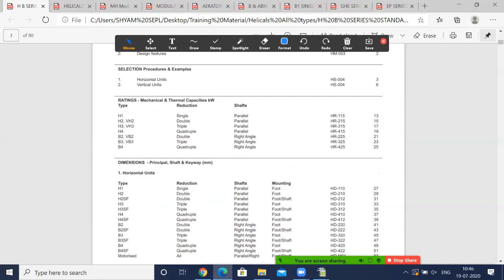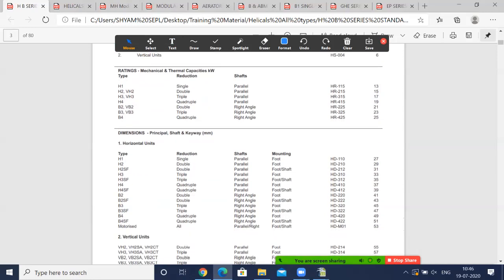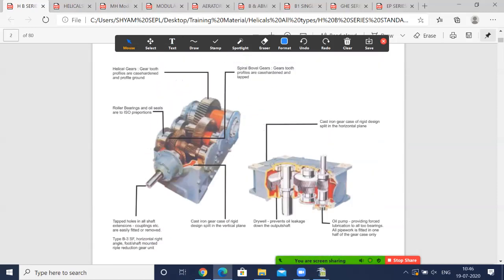H1, H2, VH2, H3, VH3, H4. So till four stage there are there. Then you have the right angle gearboxes. These are known as bevel helical gearboxes. In this gearbox, suppose the output is hollow. You can even get an output hollow. Normally it is solid. Hollow is very rarely used, but if you require hollow, then it will be named as, suppose this one is bevel, so B. Then this is first stage and second stage. So total three stages. So it is B3, but output hollow. So SF. SF is for shaft mounted. Okay, so name is B3SF.